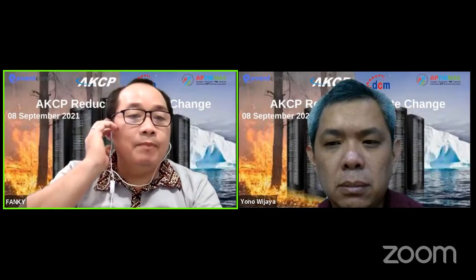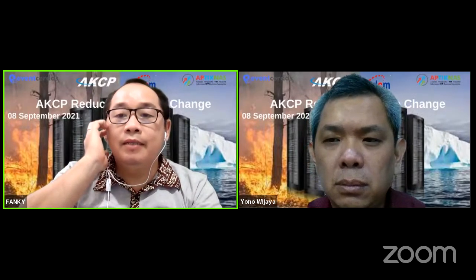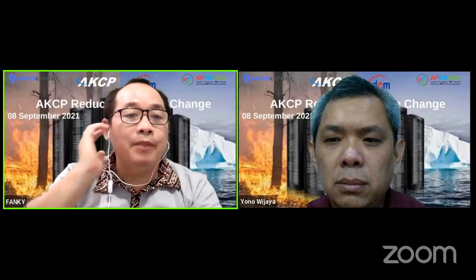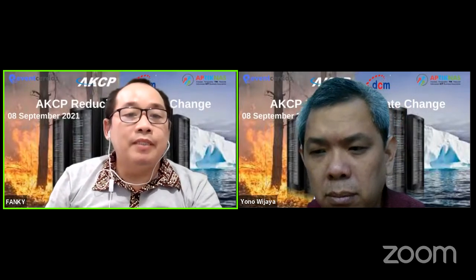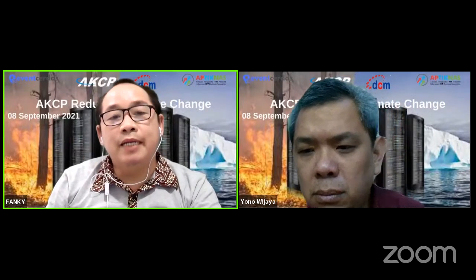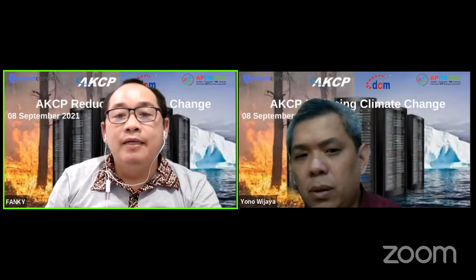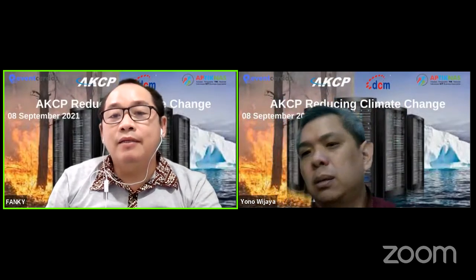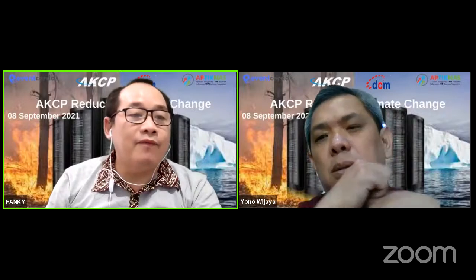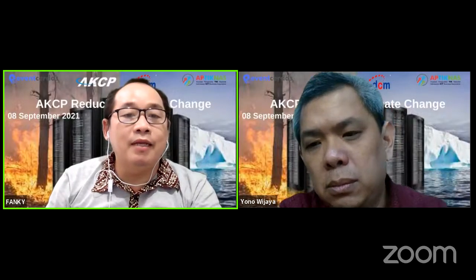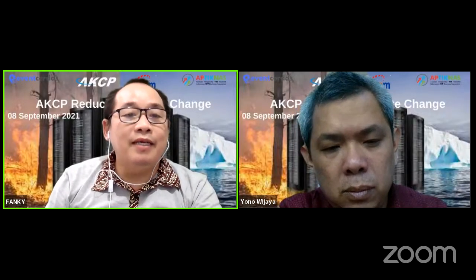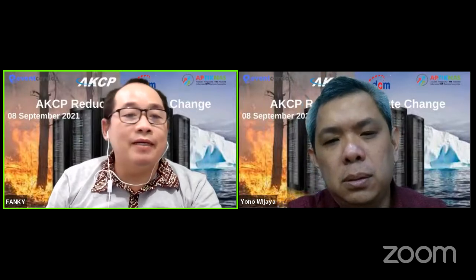I think this is from Pak Arifandi, more on, does the PUE of 1.0, that 100% free cooling from outside air, can be too risky, that the outside air is dirty and has uncertain condition that leads to damaging the device? I think it's valid for Indonesia, yeah? What do you think, Nicholas?